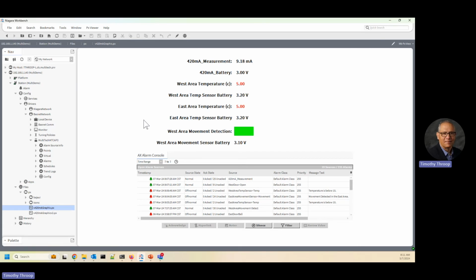But here we have a list of devices, and you'll notice that the temperature sensors are below the alarm. That's because I stuck the leads in some ice water. So we'll take them out of the water and heat them up and see that the temperatures go back to normal, because my alarm is between 10 and 25 Celsius. You can see they've gone above the low alarm threshold, and now they're operating in the normal temperature range. If I turn up the 4 to 20 milliamp sensor beyond 10 milliamps, that will report an error condition as well. And below here is a list of the alarms.